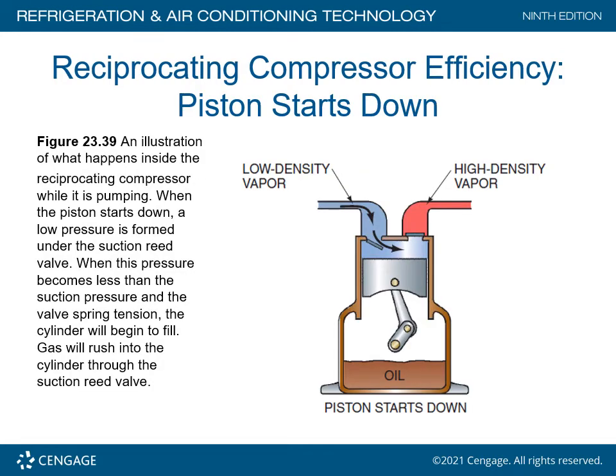Inside a reciprocating compressor — similar in a simplistic form to an automobile engine — when the piston starts down, low pressure forms under the suction reed valve. When the pressure becomes less than the suction pressure plus the valve spring tension, the cylinder begins to fill and gas rushes in through the suction reed valve. These reed valves can break, and the cause is simple: liquid. Compressors are designed to pump refrigerant vapor, not liquid. High density vapor comes off the discharge side.